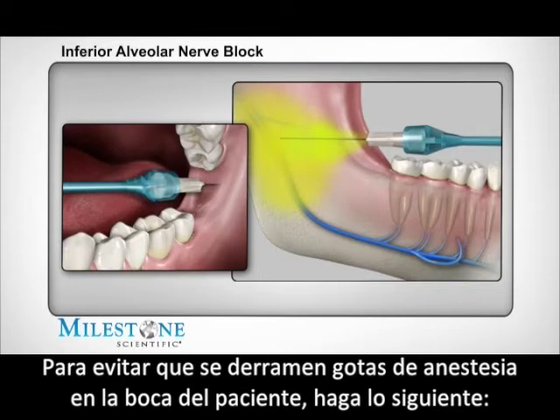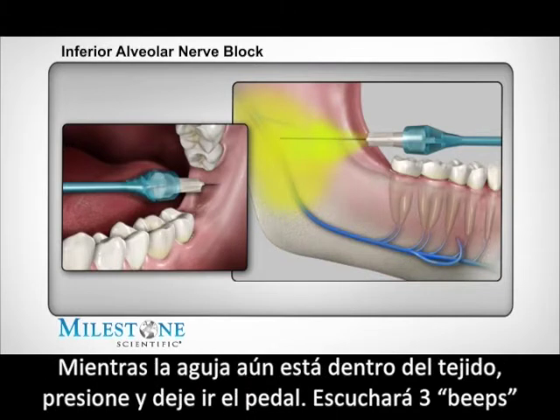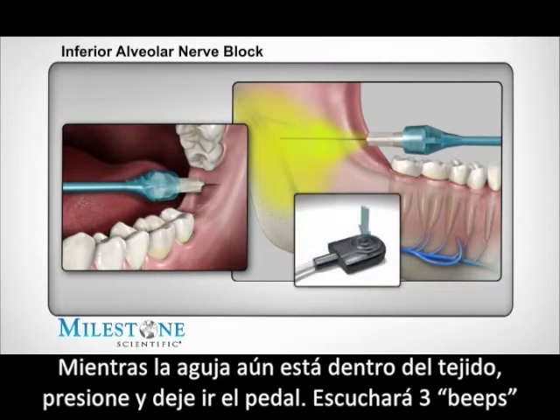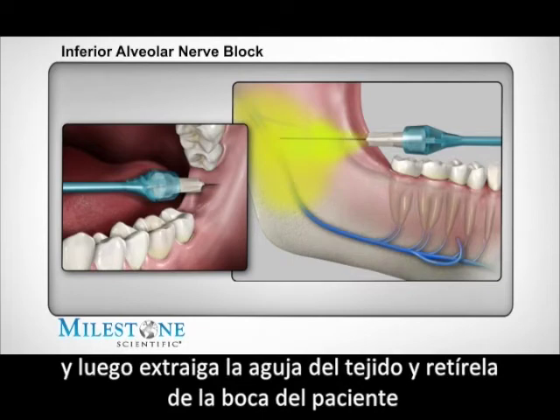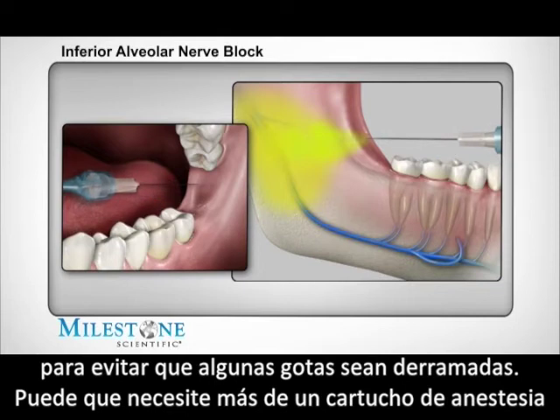To avoid anesthetic solution spray back into your patient's mouth, perform the following: while the needle is still embedded in the patient's tissues, depress and release the foot control pedal. Count three beeps after releasing the foot control, and then totally remove the needle from the patient's mouth. Direct the needle away from the patient, as a small amount of anesthetic solution may still be present.